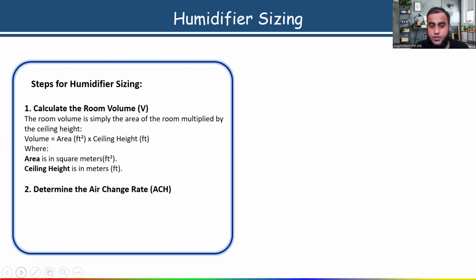Then the second step is to determine the air changes rate. This is a very important factor here. Air changes rate means the ACH value, air changes per hour. It means for that space where you are supplying conditioned air, in 1 hour, how many times do we have to change the air? Air changes means what?